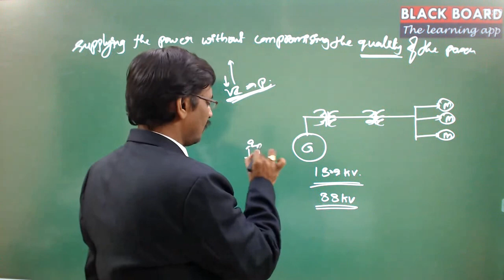I square R loss is directly related to heat - it's another way of expressing the heat produced as part of generation. This heat needs to be cooled or compensated with some kind of coolant. That's why around the periphery of the alternator there is coolant oil circulating with pumps, continuously cooling the winding.